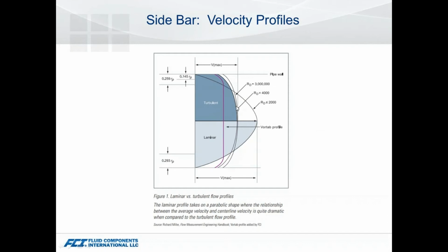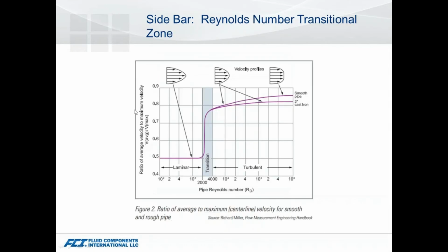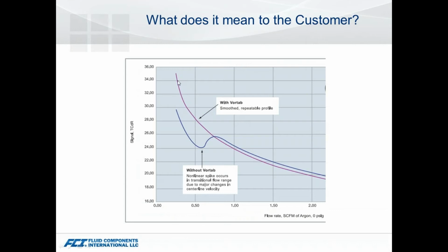If we go with that Vortab flow conditioner, we create that very repeatable flat profile the instrument's calibrated to, because we're calibrating the spool piece. One of the main drivers for doing that is that with these smaller line sizes, a lot of times we're getting into the Reynolds number transitional zone. In that zone we have a nonlinearity situation, because the sensor is seeing neither laminar nor turbulent flow. So we have this fishhook effect.